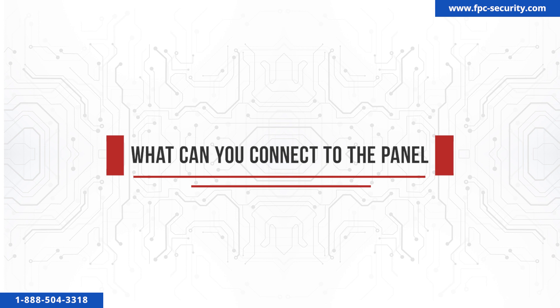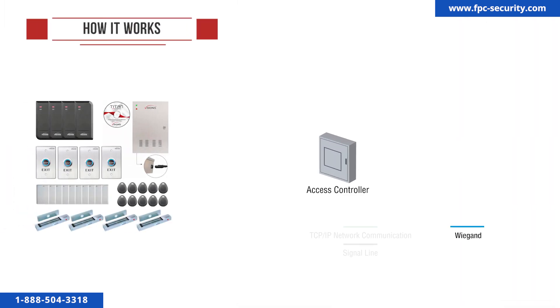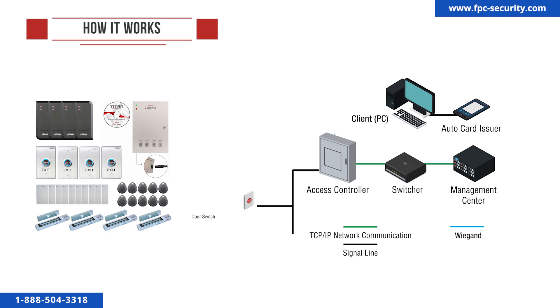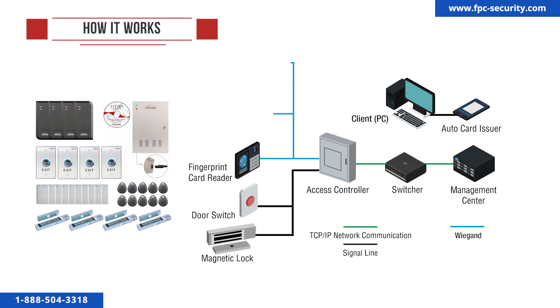Our access control panels are able to connect to any Wiegand 26 or 34 bits keycard card readers, to any 12VDC locking device, an exit device such as exit buttons, wireless receivers, PIR motion detectors, etc., by hardwiring these devices to the panel on its corresponding terminal blocks. This illustration shows a typical installation.